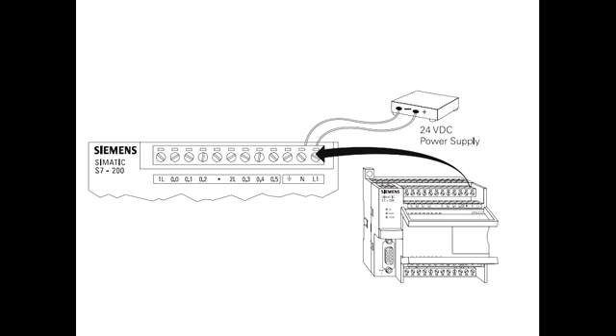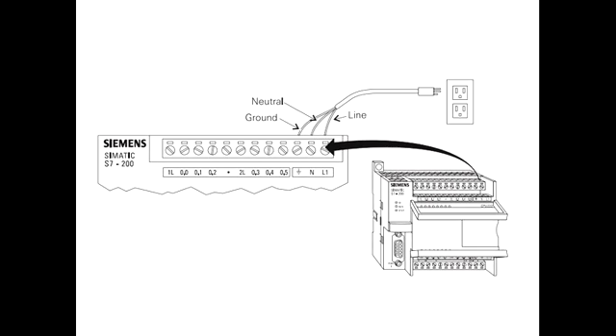External power supply sources: An S7-200 can be connected to either a 24 VDC or a 120 or 230 VAC power supply depending on the CPU. An S7-200 DC/DC/DC would be connected to a 24 VDC power supply. An S7-200 AC/DC/relay would be connected to a 120 or 230 VAC power supply.